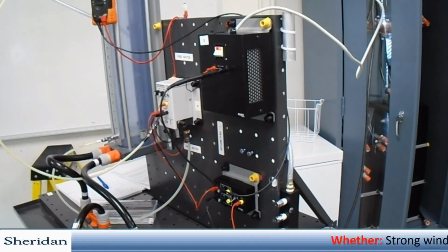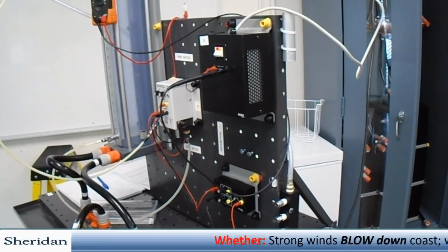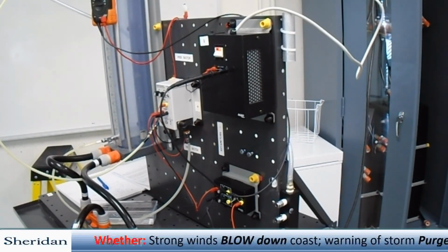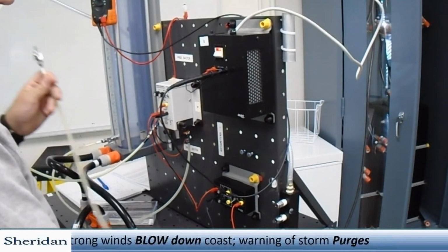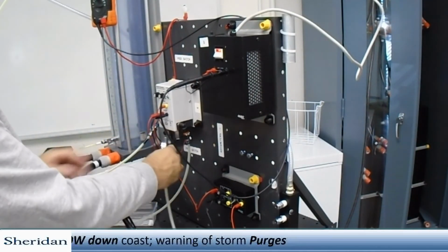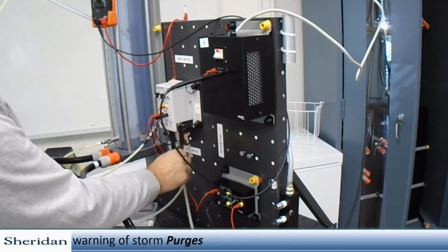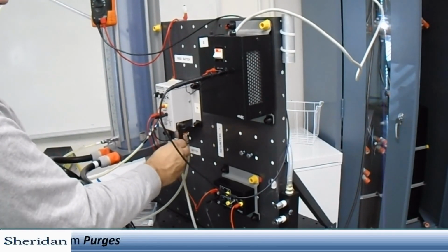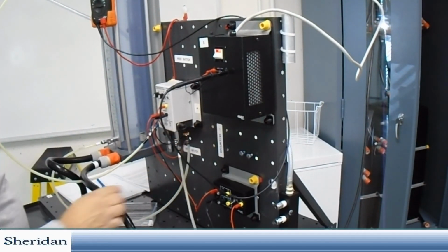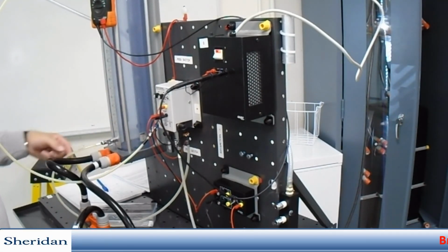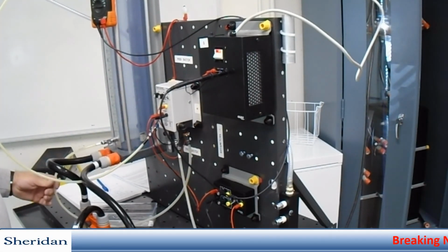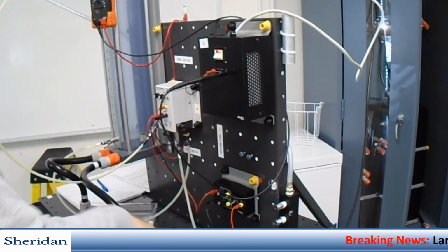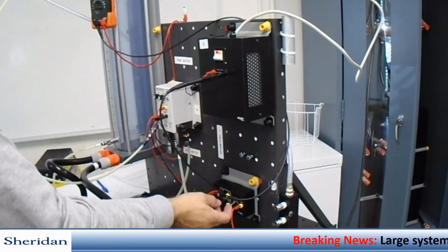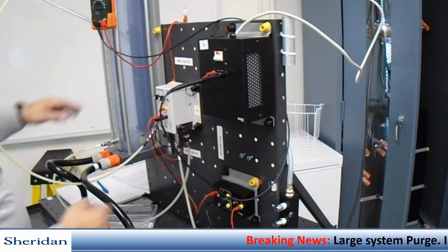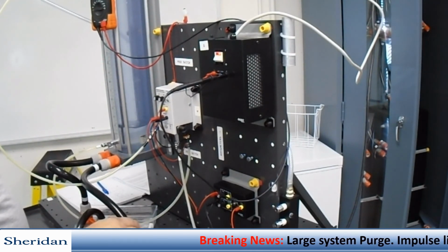We're going to blow out the trapped air in the system. To do that, we're going to use a blow-off line. We're going to put one end into the tank, the other end into the high-pressure blow-off bleeding valve port. Make sure it's snapped into place. Right now our tank is empty, which means our high-pressure impulse line is full of air. So we're going to make sure the valves are open. I'm going to turn the pump on, and we're going to fill it up to about halfway.